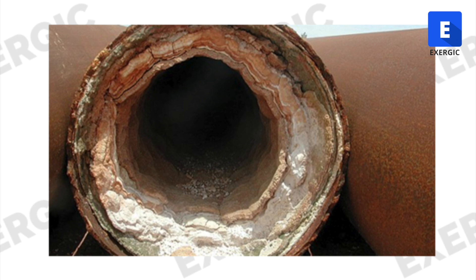More of this kind of dirt accumulation will happen. Making it look nice is not our purpose — our purpose is to make sure that the resistance of the tube walls should not be high. It should be at a desired value from the heat transfer point of view in the condenser of the power plant. But as a result of this accumulation and increase in the thickness of the tube wall, the conduction resistance is increasing over time.